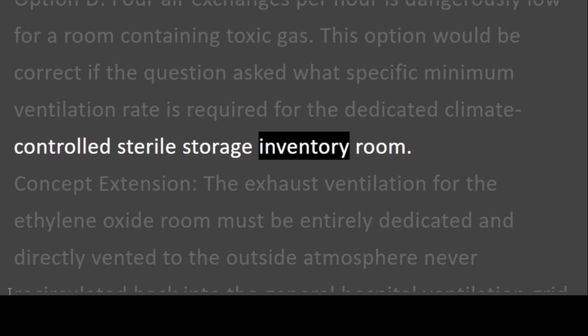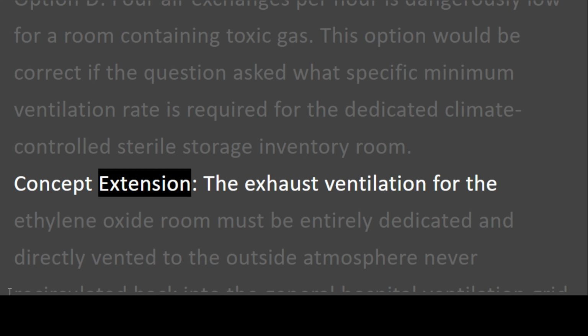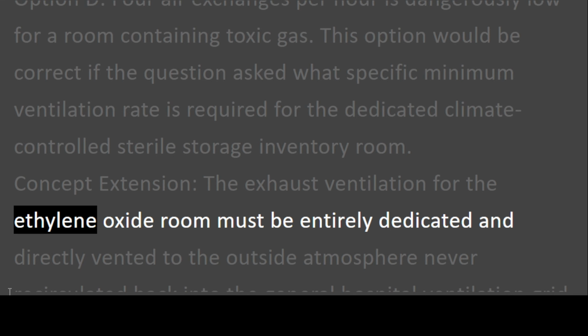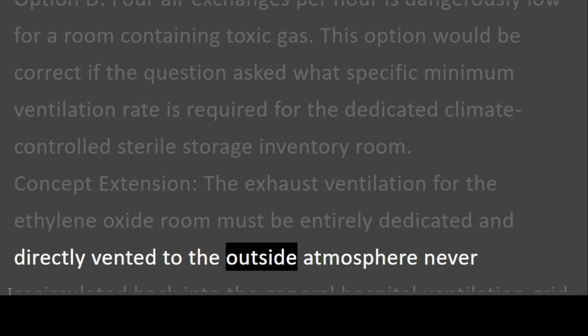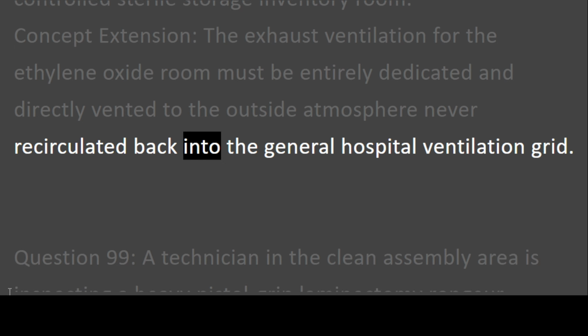Concept extension. The exhaust ventilation for the ethylene oxide room must be entirely dedicated and directly vented to the outside atmosphere, never recirculated back into the general hospital ventilation grid.